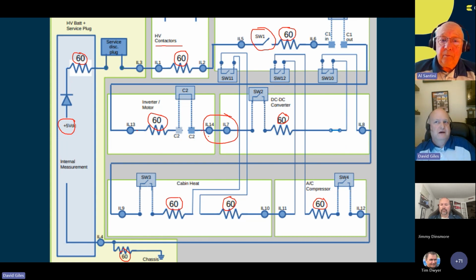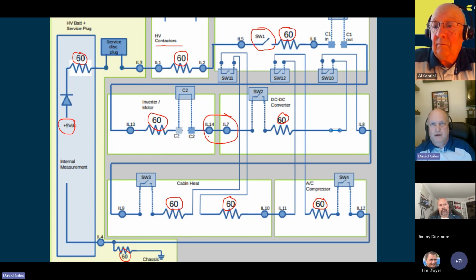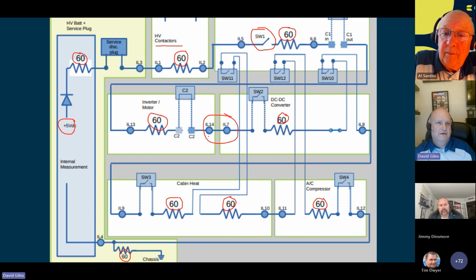If it sees no voltage drop over, for example, IL1 and IL2, it knows there's an open in that circuit, meaning something has been disconnected. Based on where it sees the voltage drops in that circuit, it knows the integrity of that circuit is good. In fact, OEM manufacturer information will have voltage drops specified at different points in the circuit for testing to ensure its integrity.